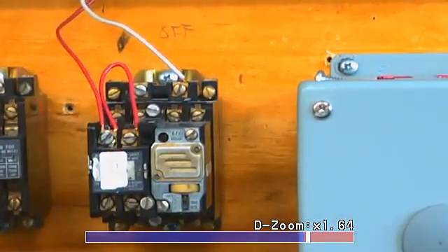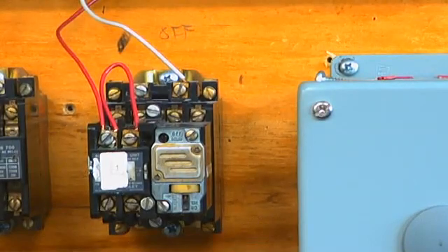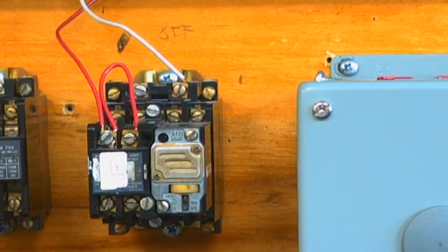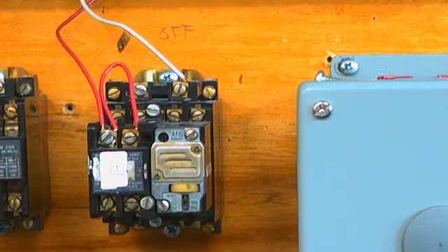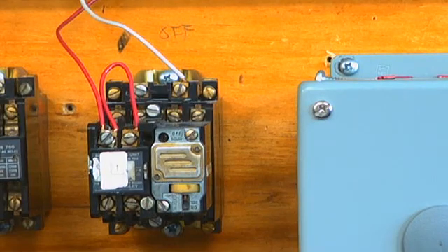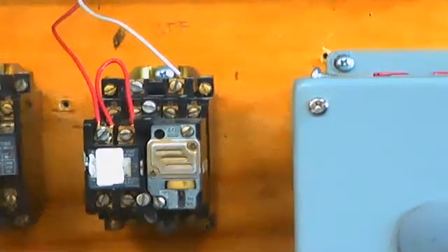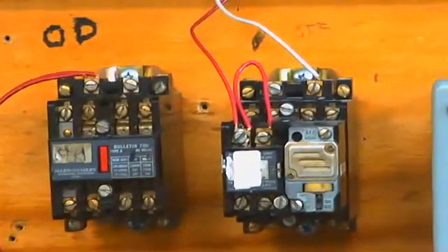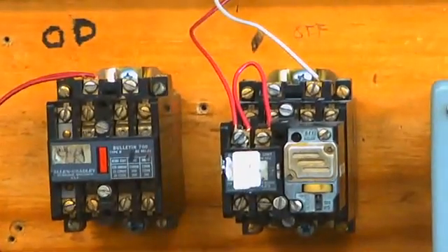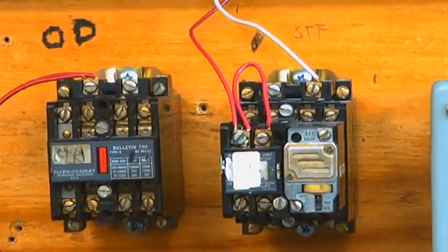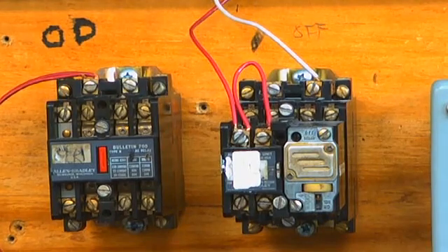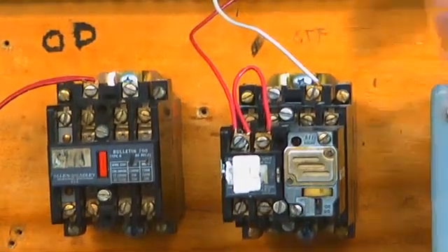All right, so where is the coil on this timer? Yeah, the top 2 screws. There's a neutral landed on the right-hand side, and the left-hand side is where you would energize the coil. And this is the exact same thing, right? It's just one of those Allen Bradley Bulletin 700 control relays with 4 sets of contacts on the back.